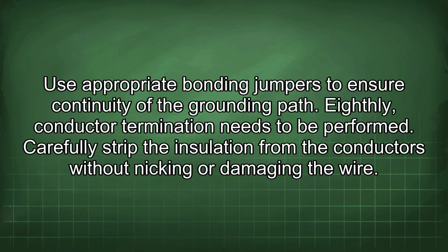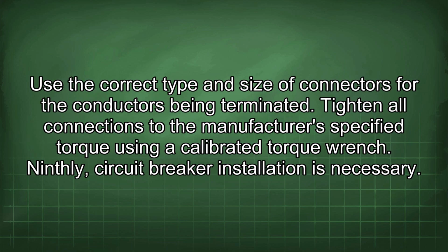Eighthly, conductor termination needs to be performed. Carefully strip the insulation from the conductors without nicking or damaging the wire. Use the correct type and size of connectors for the conductors being terminated. Tighten all connections to the manufacturer's specified torque using a calibrated torque wrench.